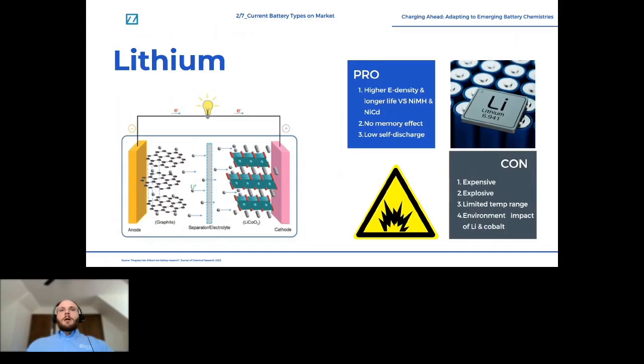Lithium ion batteries last around 2 to 3,000 cycles, while lithium iron phosphate batteries can last even longer, up to 10,000 cycles. And these numbers can vary widely based upon the environment the battery is in, the temperatures it's in, that sort of thing, as well as the amount of recharge and discharge. Lithium ion has the positives of being lighter weight, more energy dense, having a longer life, and does not require the ventilation compared to these older technologies.